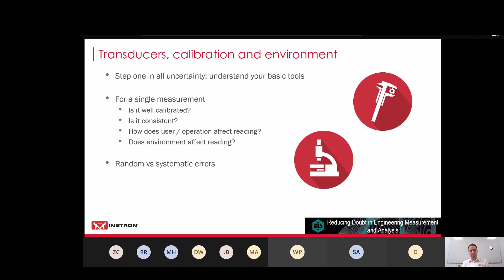So practically, we have verification procedures. We calibrate our device, whatever it is, and then we should, as good practice, verify that when we've got it in place and we come to use it, or before we use it, in fact. And that means that we can systematically declare an uncertainty on just that one measurement. Now, it might be proportional with the scale of the reading. This is quite common with electronic transducers, certainly within our business, where a lot of them are strain gauge based. So the error is declared as, for example, arbitrary figure, 0.1% of the reading. So the absolute error will increase with the size of the reading. Or it might be absolute.